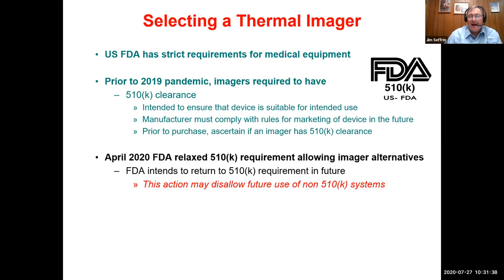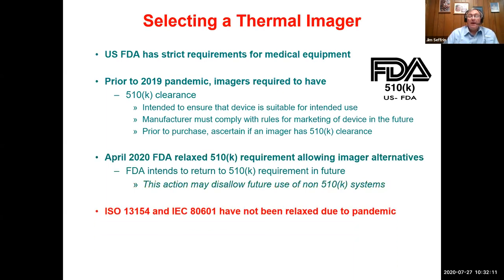Now, for those of you who have an instrument that is not 510K cleared, as I said a moment ago, it's possible to use it at present. However, you need to understand that the FDA has stated in their publications that they intend to return to a 510K requirement in the future. So before you invest a lot of money into non-510K cleared systems, know that if this is your sole purpose in making your investment, if the FDA returns to the 510K requirement, it could disallow future use of non-510K cleared systems. Now, for those of you working internationally, you should be aware that ISO 13154 and a document which is incorporated by reference, which is IEC 80601, have not been relaxed due to the current pandemic.